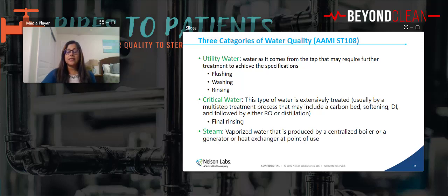And when you think about it, the non-condensable gases, the minerals, the metals that pass through the water can go into the steam chamber and create these discolorations that you often see on the devices or on the trays, the hard water stains that you see on the lids of the trays and on the devices. Those are all there through that system. So it's very important to ensure that the steam portion is also noted and discussed. So that was why it was added.